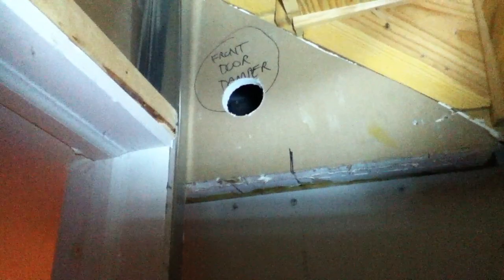Here you can see the edge of the double 5/8ths drywall alongside the closet here. I'm going to seal that up. The drywall is already done inside the closet here — that's probably the hardest thing. Just a viewing port for up in the bulkhead. So there's that, in case anybody ever needs to see what was done.